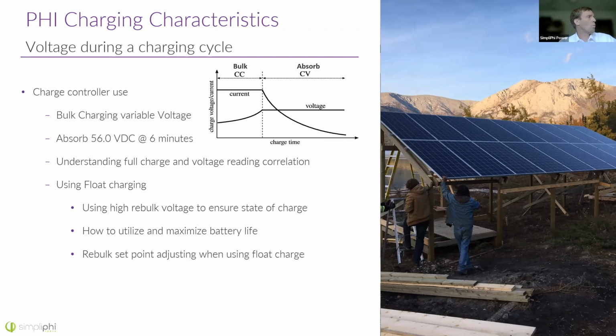Okay, so what's next on this charging cycle? There's also a rebulk voltage. The rebulk is the voltage at which, as the battery gets used, once you hit that setting, the charge controller will start to charge the battery again. So let's suppose you set the rebulk at 52 volts because you want to maintain a high state of charge for a battery backup situation. Then the rebulk would be when that battery starts charging again.